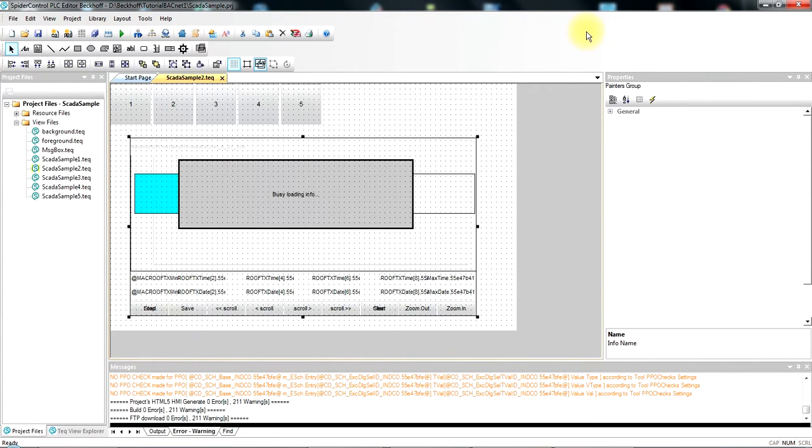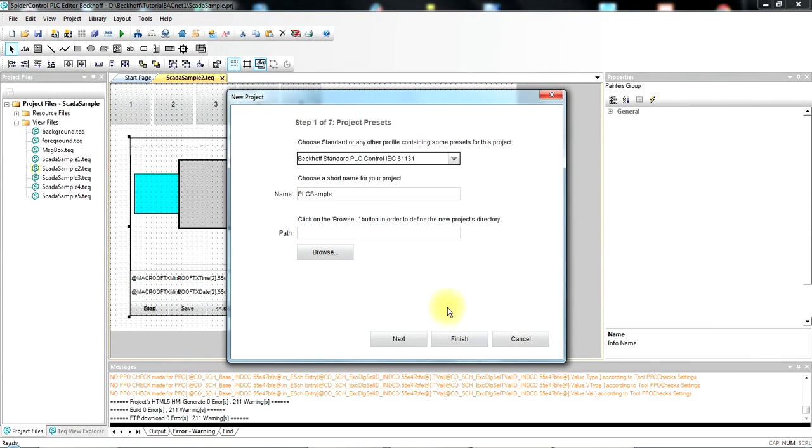So next steps, we go to the software. You would like to create a new project supporting BACnet. If we start the wizard, we choose the template for Beckhoff BACnet and PLC control. So this will allow us to access variables from both the BACnet stack as well as from the TwinCAT IEC 61131 software. We give it a name.